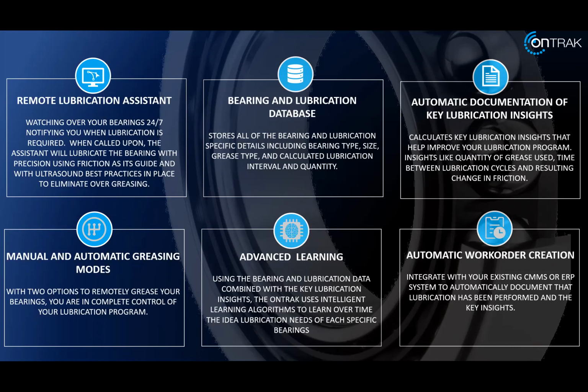And there's a reason we still want to use that feature. If anybody is a little hesitant about shifting from time-based to true condition-based lubrication using ultrasound, those numbers can help give the confidence to start extending intervals and using less grease over time. So we can start to say: hey, normally you would have greased the bearing at this time—why don't you go take a look at the friction? Try to push it out a day or two, or a few weeks, but keep monitoring that friction.